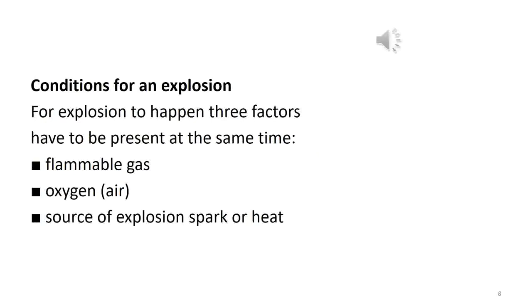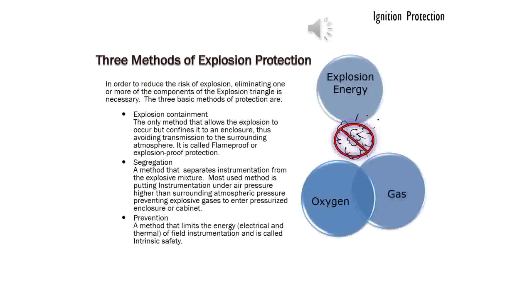Conditions for an explosion. For an explosion to happen, three factors have to be present at the same time: flammable gas, oxygen in the air, source of explosion, spark or heat. Three methods of explosion protection.